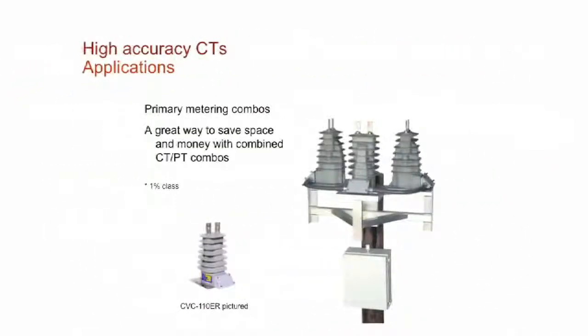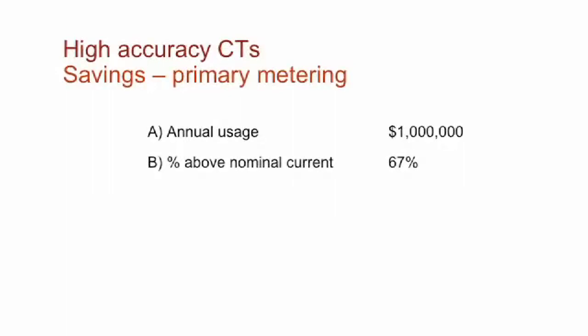We also have them in combination units. The current and voltage both can be in one installation as well. Basically, that helps for ease of installation for the lineman. Let's take a look at the savings at the primary metering level. Annual usage. I'm taking, again, my factory as an example. We pay about $1 million a year in electricity. Percent of time above nominal current. Okay, and kind of how I came up with that is my factory as this example.